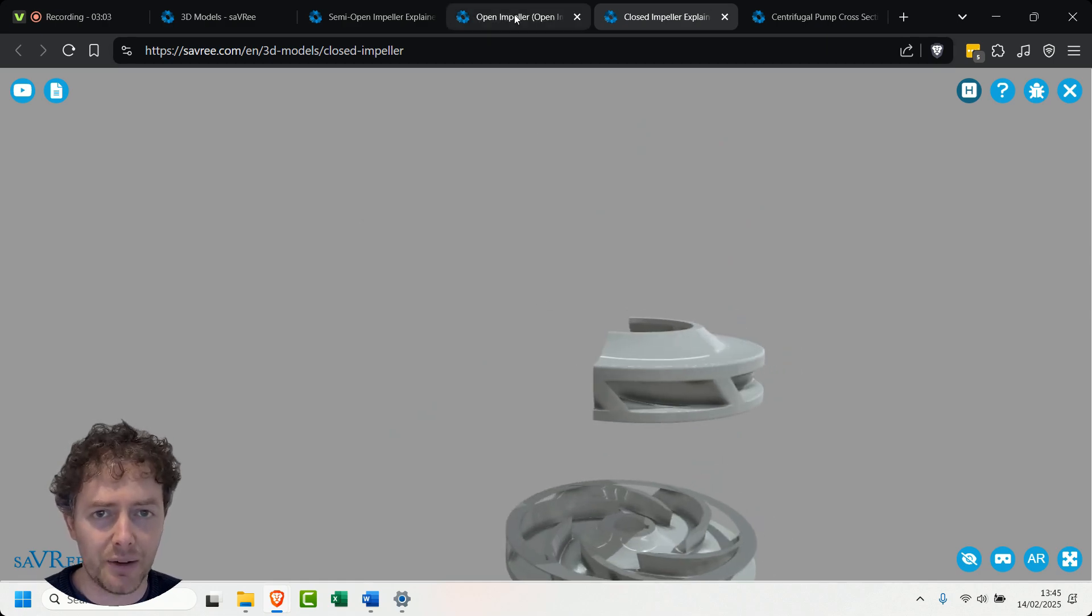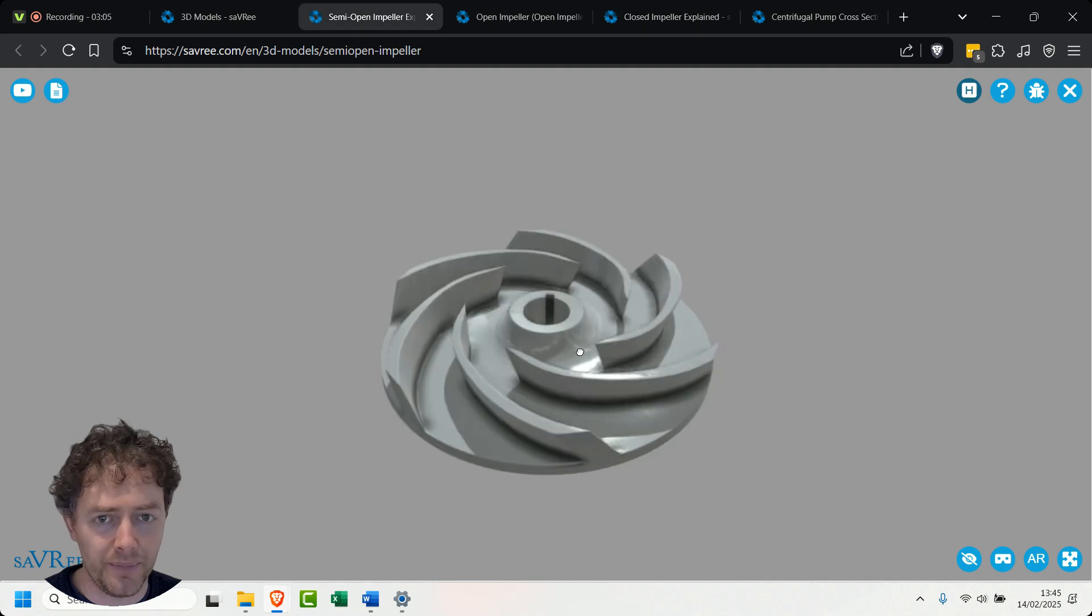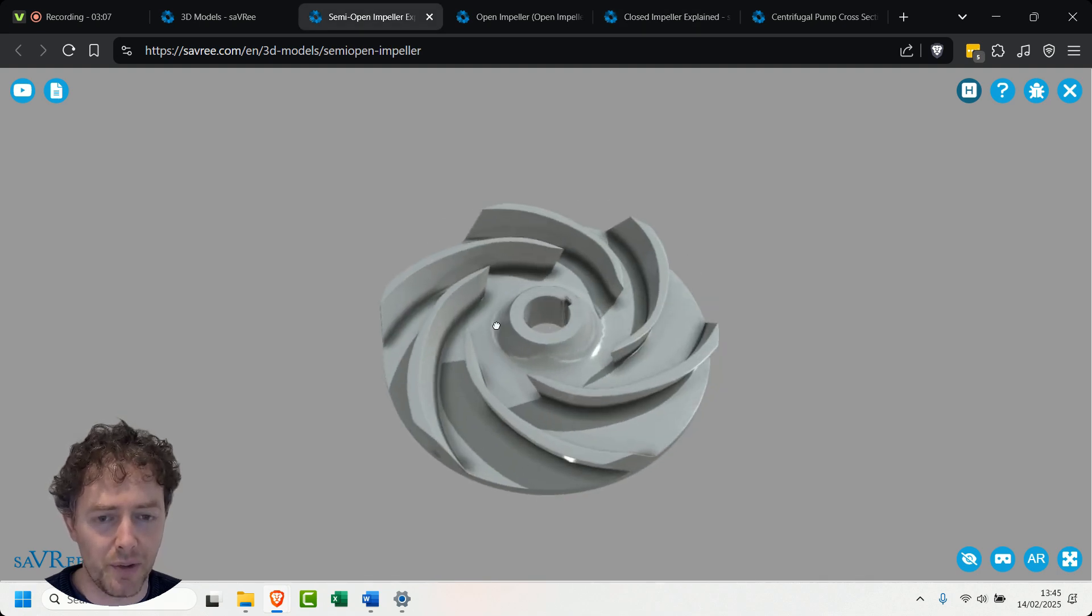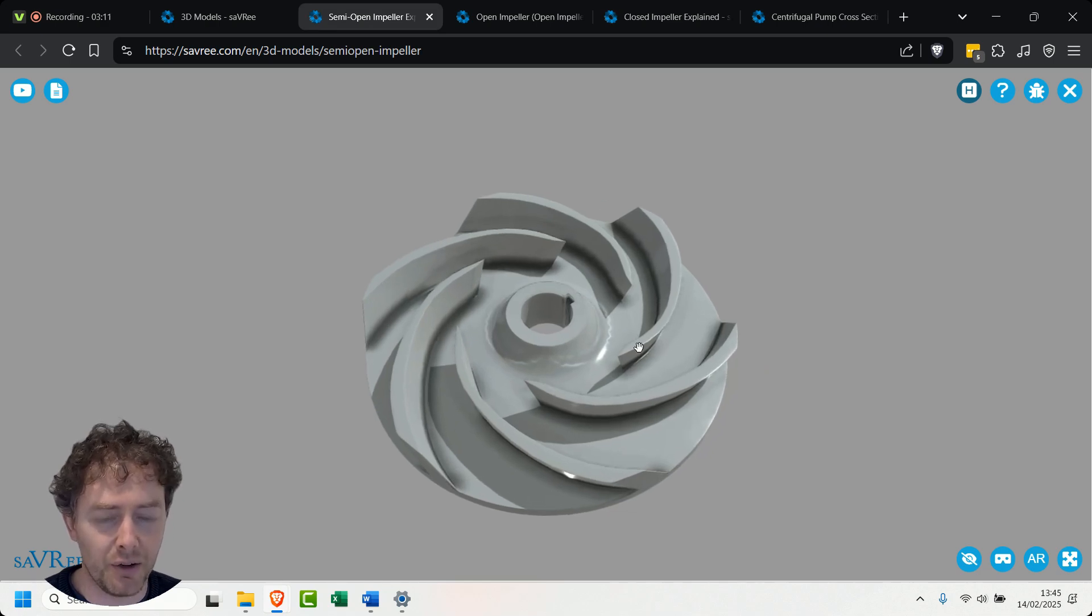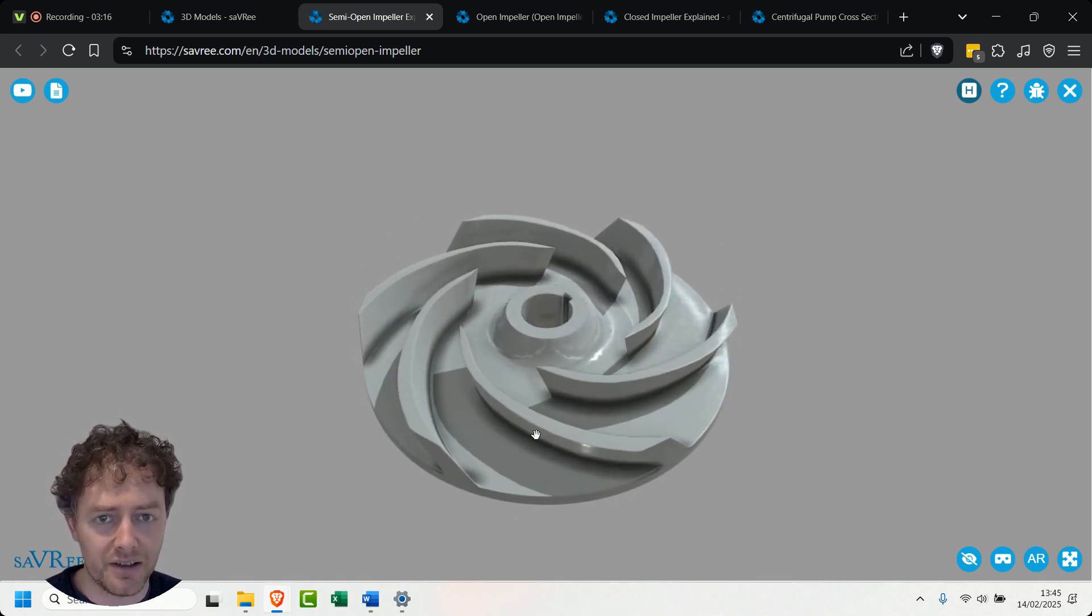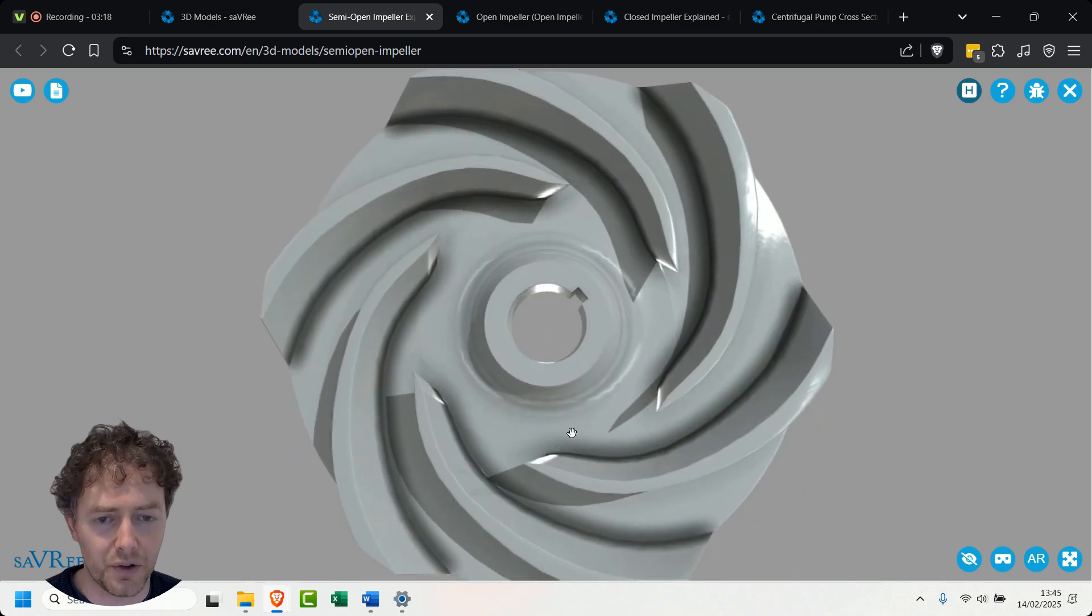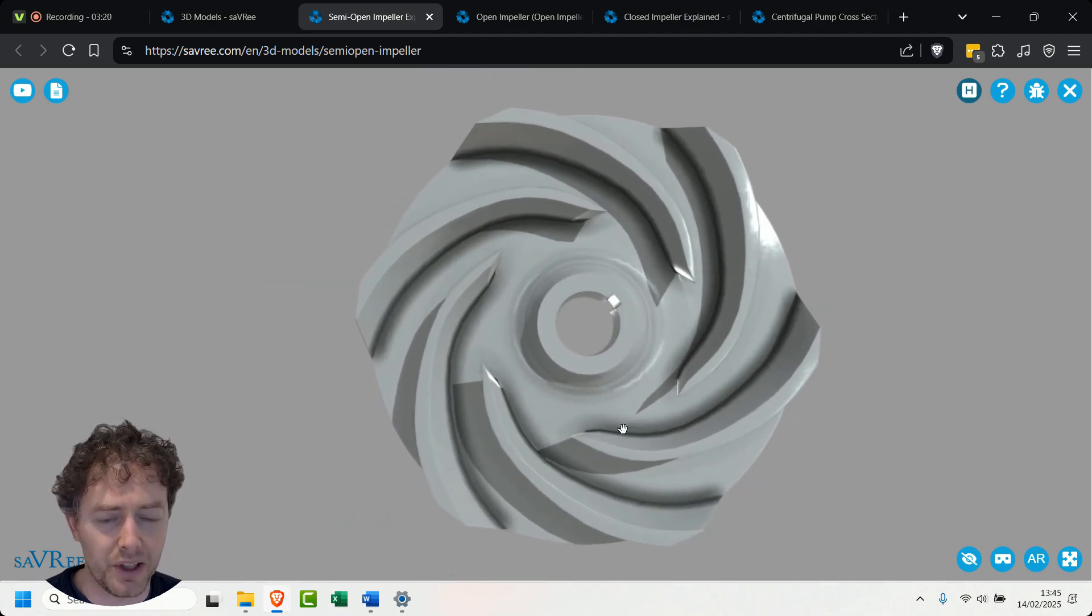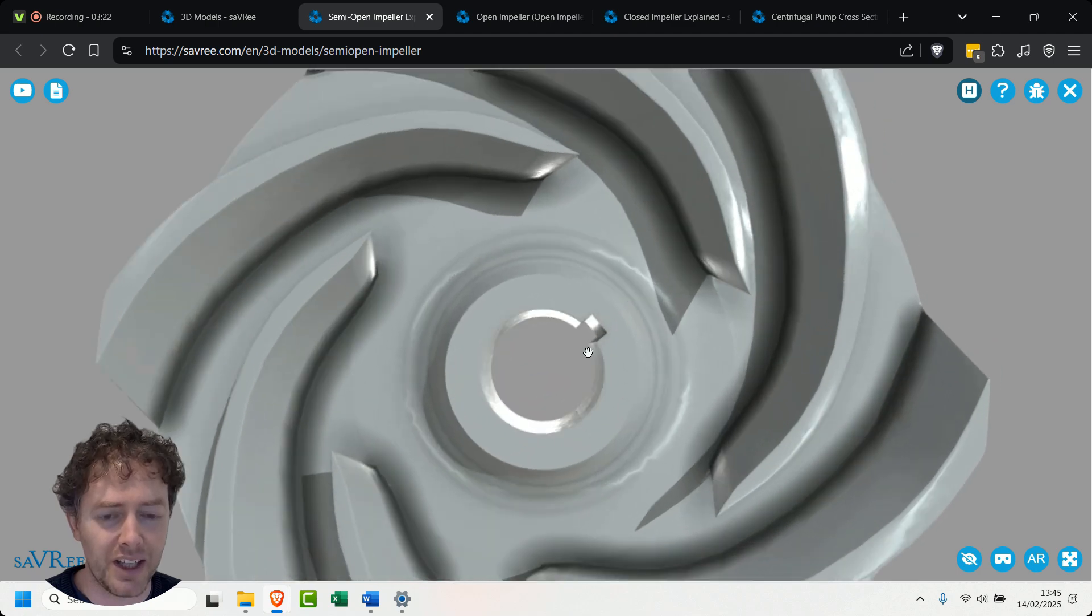Let's have a look now at the semi-open impeller. That's similar to what we just saw a moment ago but this one is how it would actually look. That is the entire impeller. There's only one shroud. The shroud is on the back side and the vanes are attached to the shroud and then the channels in between and the shaft and also the shaft key.